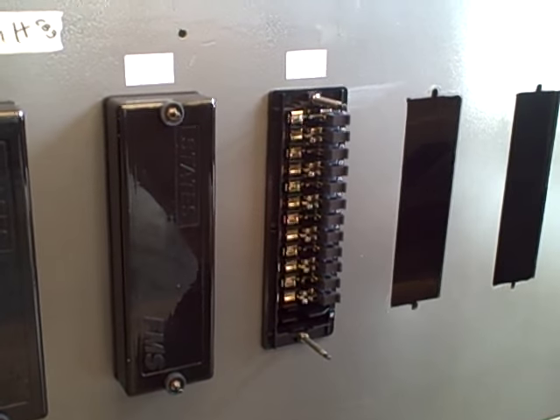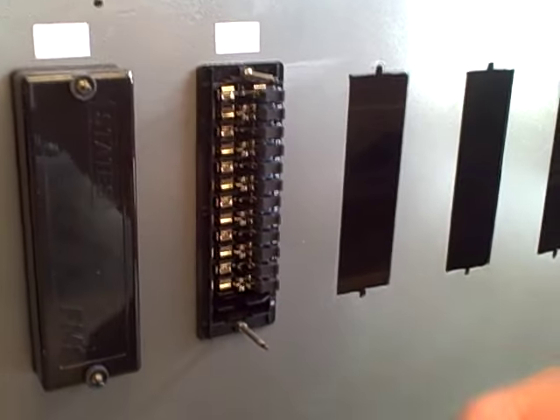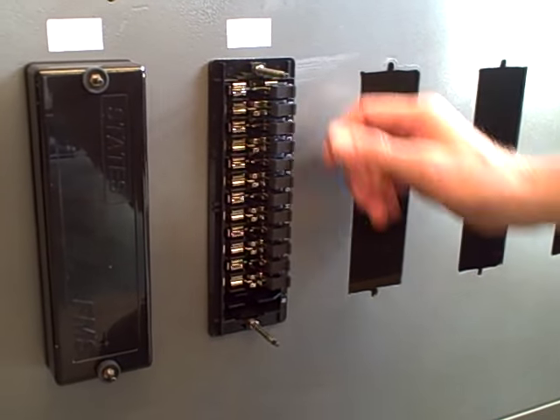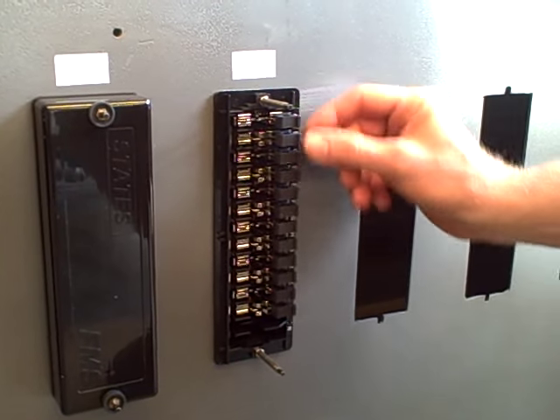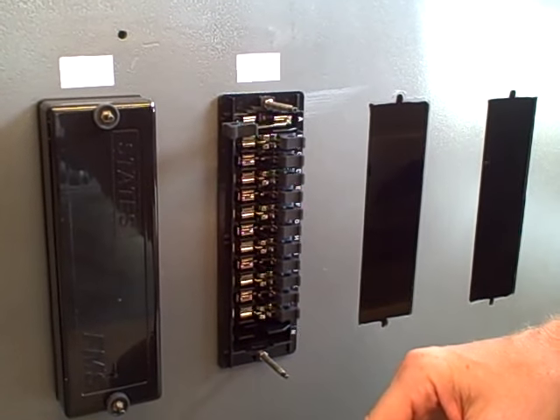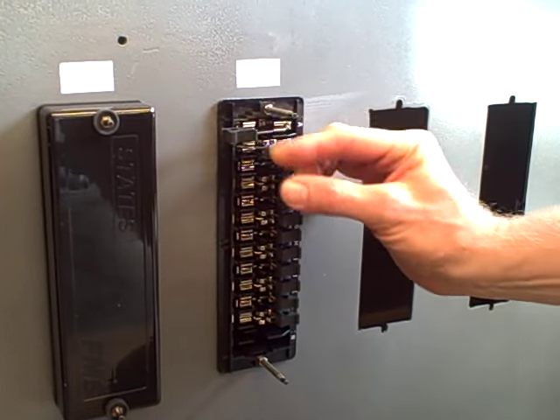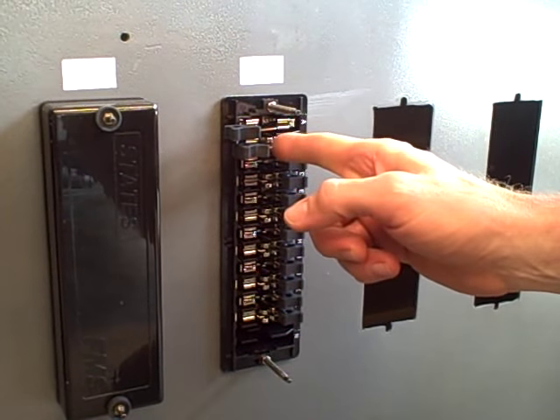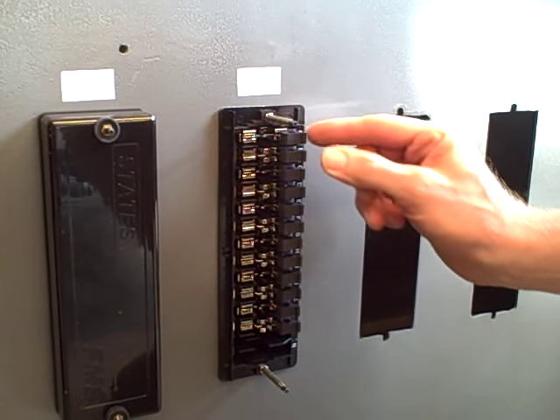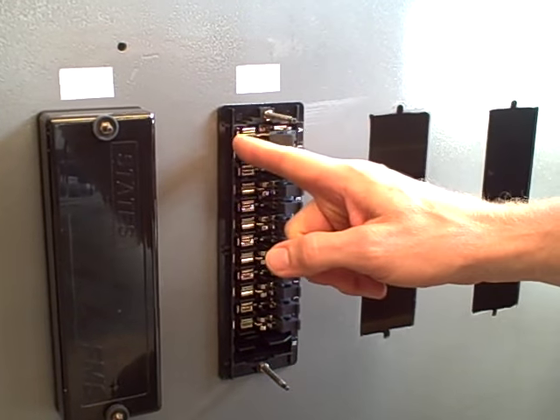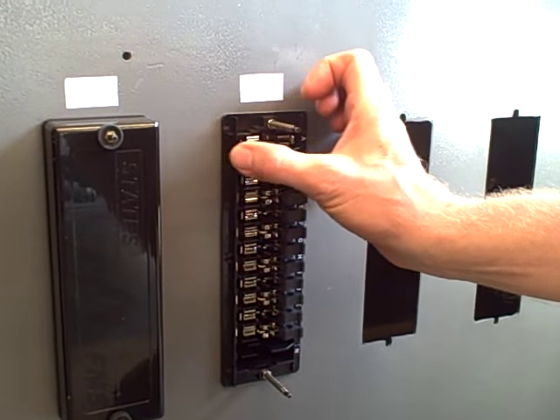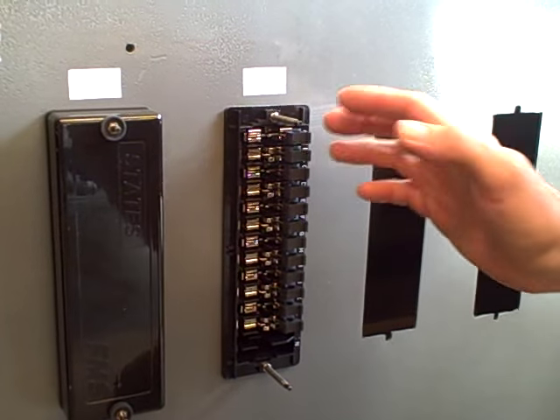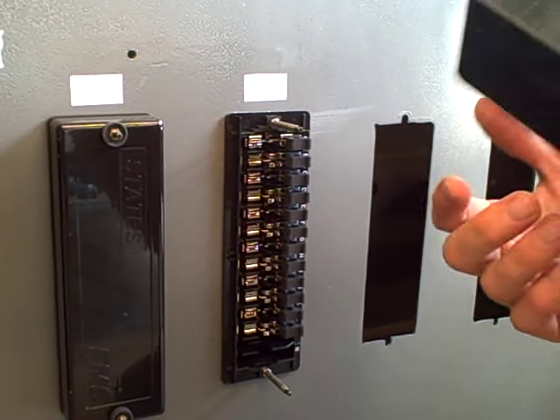So every circuit breaker we constructed has six CTs, six current transformers, three line and three load. And this CT test switch assembly allows us to break open that CT circuit for doing maintenance and also to take a CT test stab and insert there to measure current. They are shorting switches, so when you open the switch, it actually shorts the CT for safety. So you're not going to cause an actual open circuit within the CT. You simply open the wiring that goes to the protective relay.